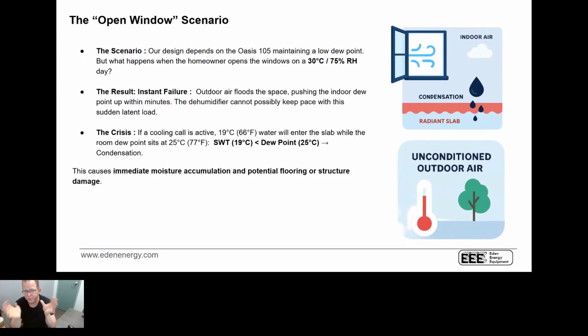Let's say we do, in fact, put in a dehumidifier. So I, in particular, picked an Oasis 105 that's designed to remove a lot of moisture out of that space. It's a high performance unit. Well, even with that dehumidifier running, if somebody opens every window in the home, this is literally my scenario. It was 30 degrees Celsius outside. The relative humidity got up to 76%. And at that point, it's just a massive flood of outdoor humid air coming into the space. And the dehumidifier just simply cannot keep up with that scenario.